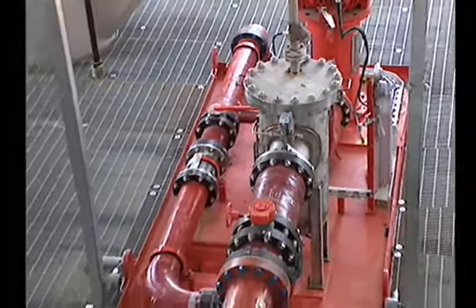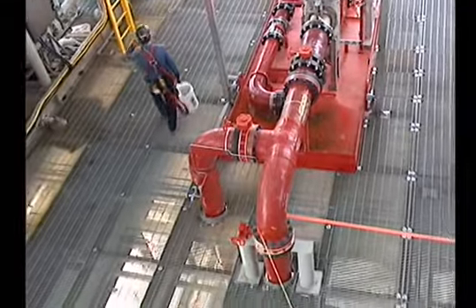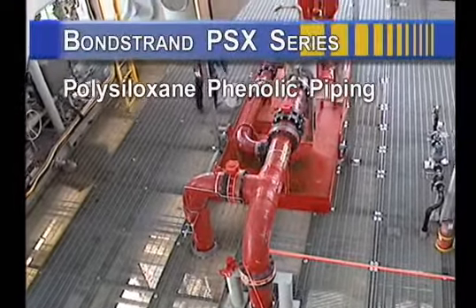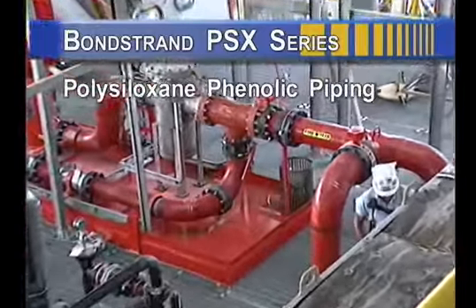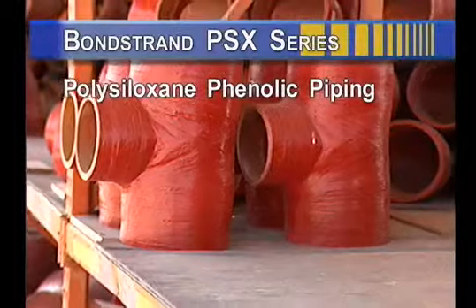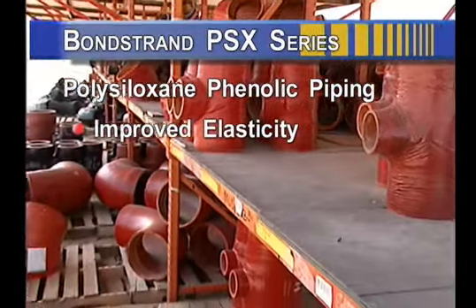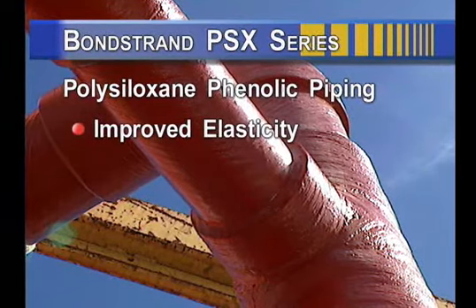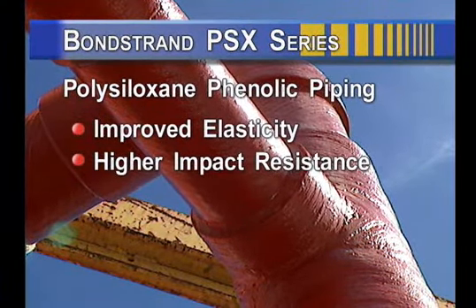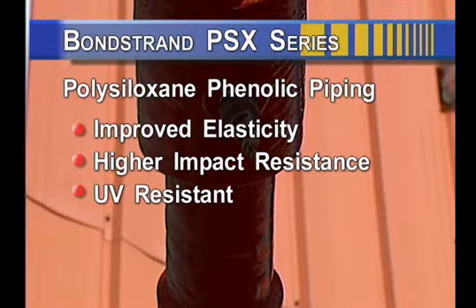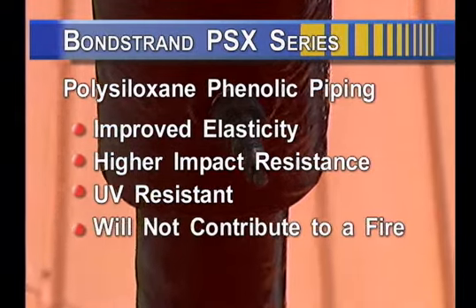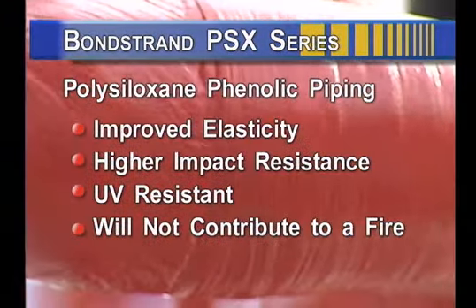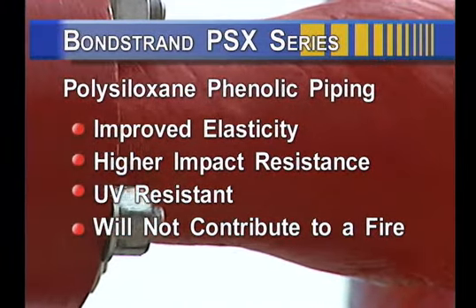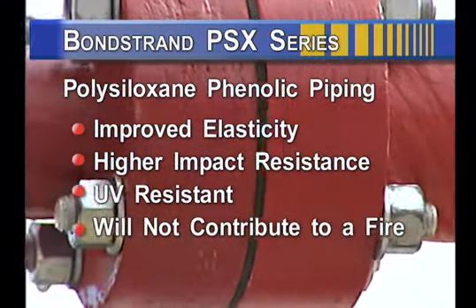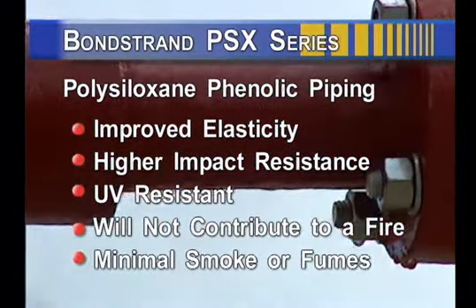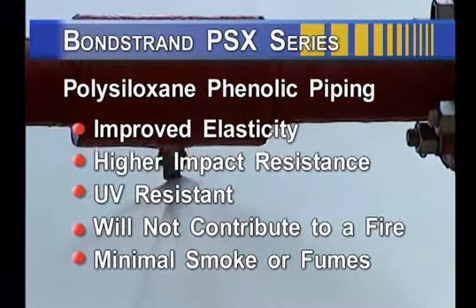To provide a safer offshore firewater system, particularly for deep-water platforms, Ameron introduced the PSX filament-wound polysiloxane phenolic piping system to withstand a hydrocarbon fire. Siloxane modification enhances phenolic resin to improve elasticity and overcome brittleness associated with phenolics. It also provides higher impact resistance and enhanced UV resistance. Ameron Bondstrand PSX products will not contribute to a fire. In enclosed spaces, most fatalities in a fire are caused by inhalation of toxic fumes produced by burning materials. At high temperature, Bondstrand PSX products generate very little smoke and minimal toxic fumes, making PSX products ideal for use in living quarters.